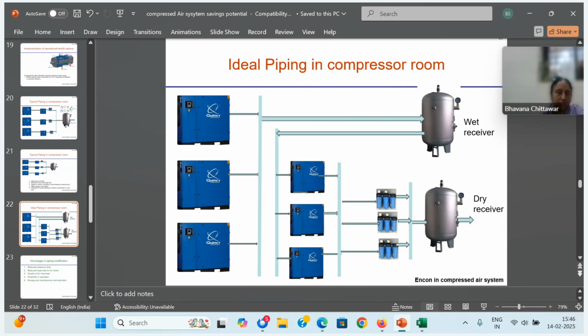Most of the heat of the compressed air gets dissipated before the dryer. Moisture is drained in the receiver. Oil also gets trapped in the receiver, so it doesn't get into the air dryer. So the load on the air dryer is reduced. There will be uniform flow across the air dryer. Pressure drop gets reduced. When oil filters are in parallel, the pressure drop is less. You can bypass some filters and replace them online, while the compressor and dryer run through other filters. So this is the perfect system.